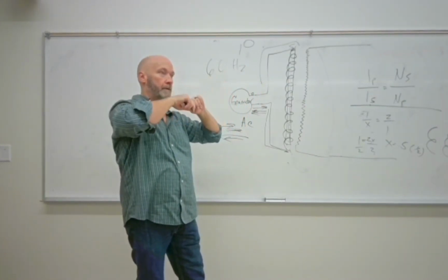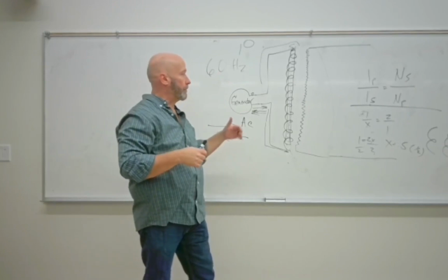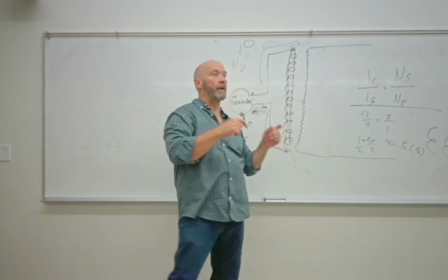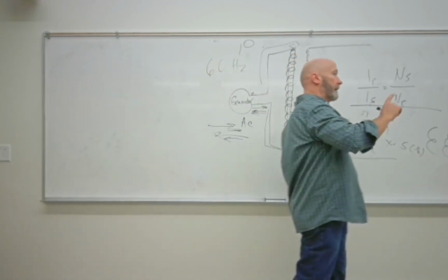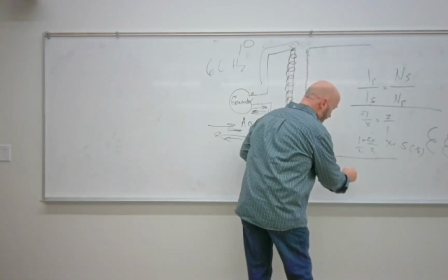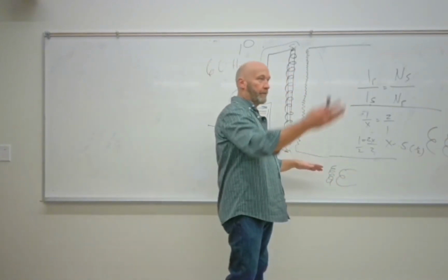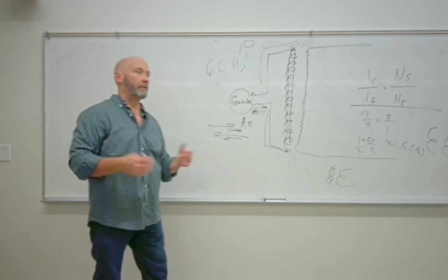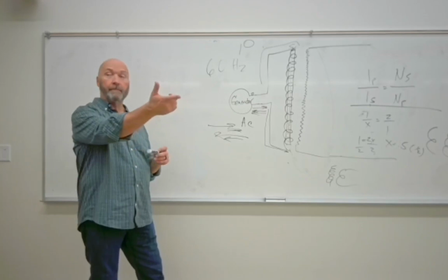Okay. So voltage in both the filament transformer and the step up transformer is directly proportional to the turns ratio. Now, where you might have gotten inverse is that the filament transformer is turned around. Our filament transformer would have more turns on the primary side than on the secondary side. The purpose for that is to take our maybe 250 volts and drop it down to 25 volts. Why do we only want 25 volts on the filament? So it doesn't burn up. That's one.